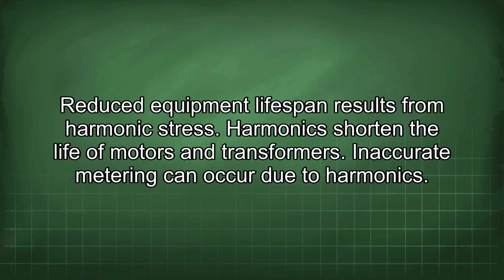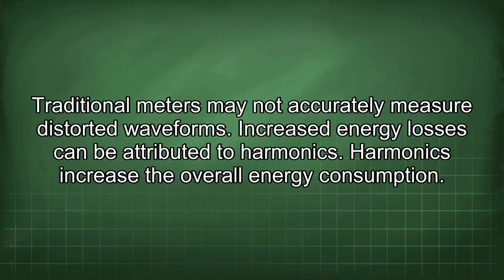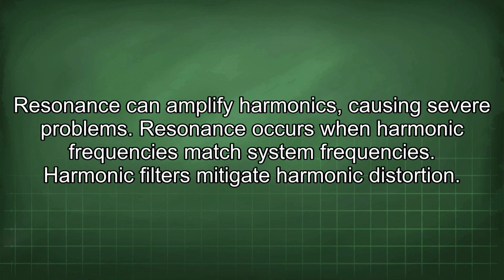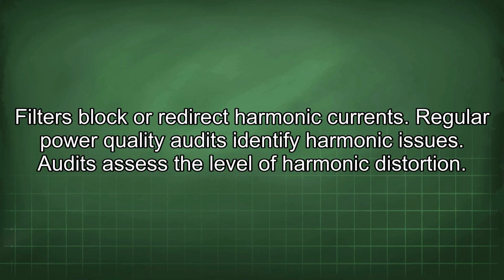Inaccurate metering can occur due to harmonics. Traditional meters may not accurately measure distorted waveforms. Increased energy losses can be attributed to harmonics. Harmonics increase the overall energy consumption. Resonance can amplify harmonics, causing severe problems. Resonance occurs when harmonic frequencies match system frequencies. Harmonic filters mitigate harmonic distortion. Filters block or redirect harmonic currents.